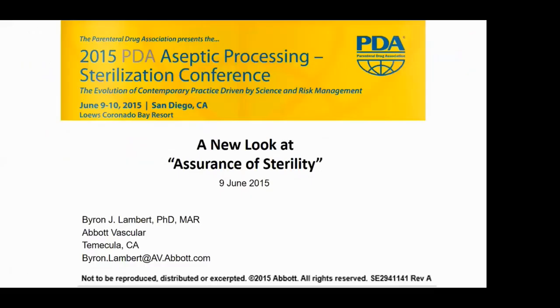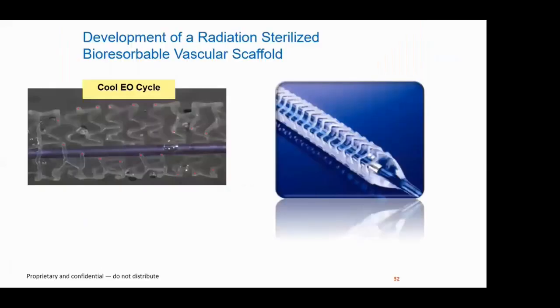So I'll show you some excerpts from a presentation several years back on this development process. The scaffold is on the right, and you can see even on a cool ethylene oxide cycle, the red dots are where the scaffold was broken. When it's sterilized, it's in the non-expanded configuration, pressed up against that blue inner member. But after EO sterilization, it ended up plasticizing either the ethylene oxide and/or the moisture in the cycle, so that when you expanded the scaffold, you got those breaks.